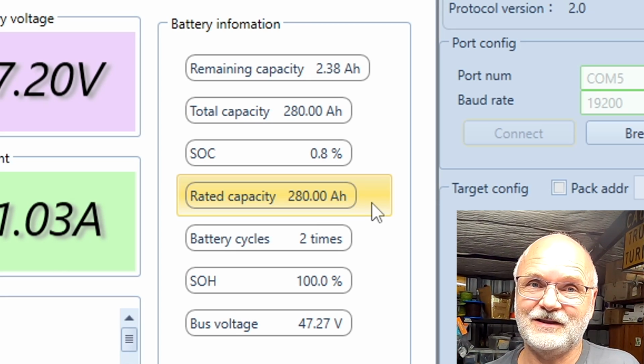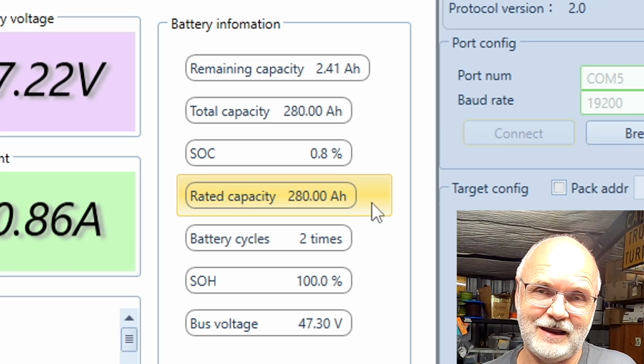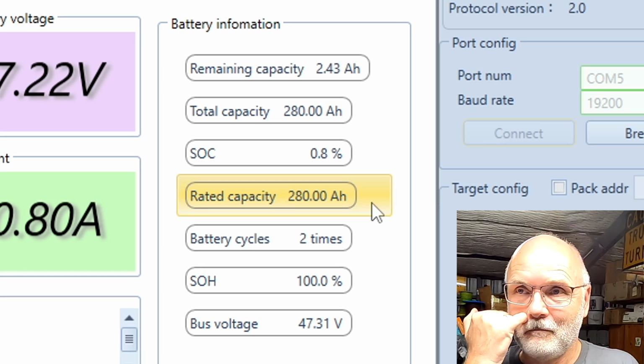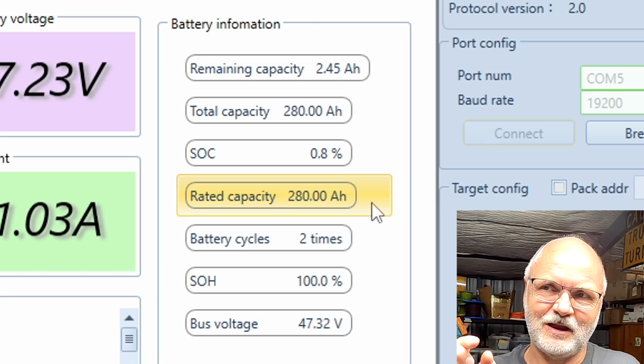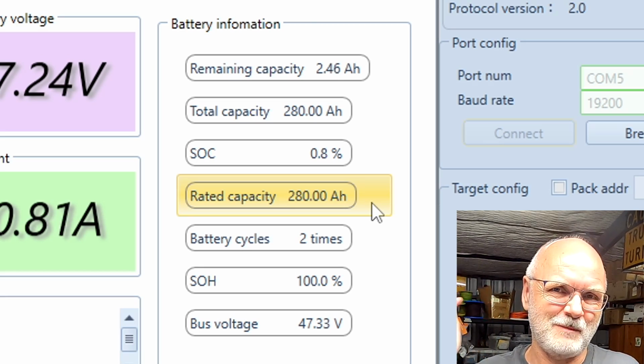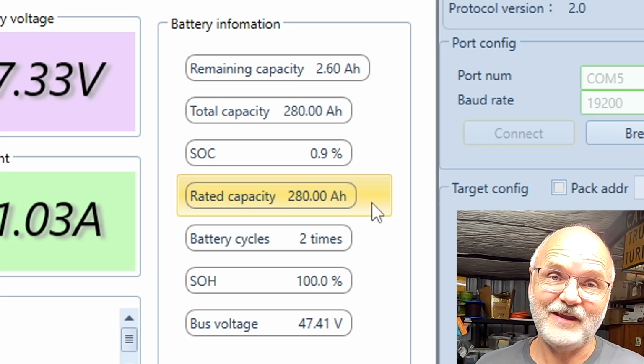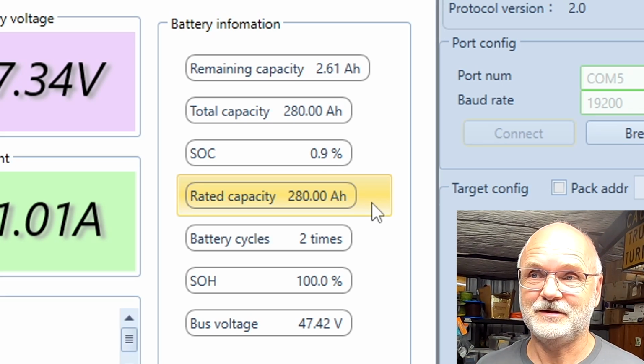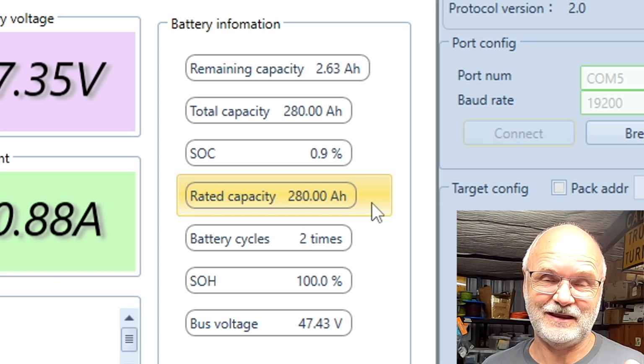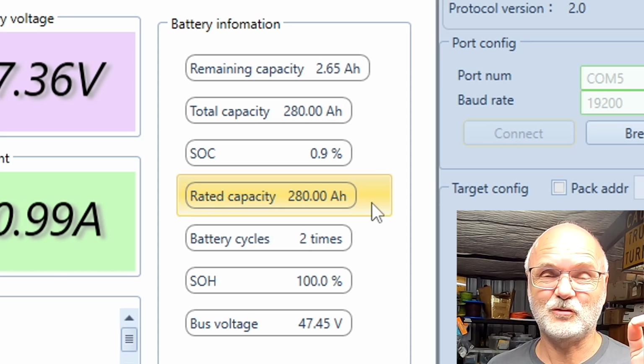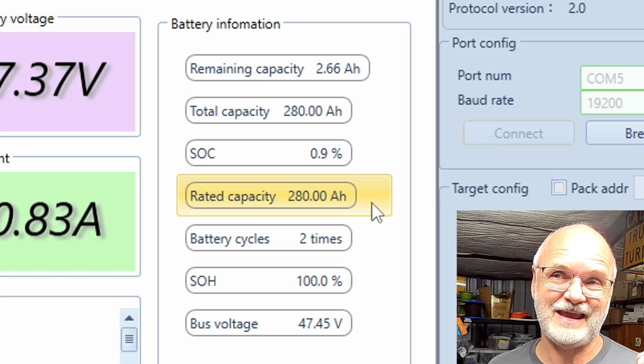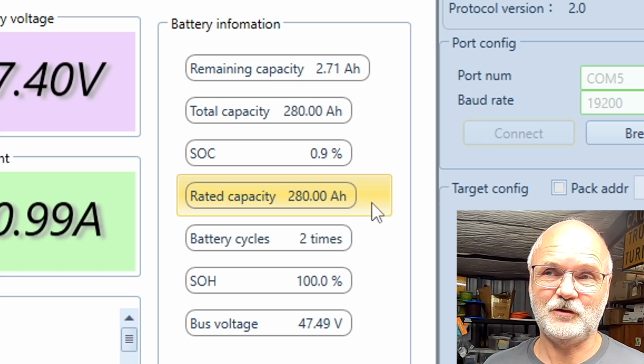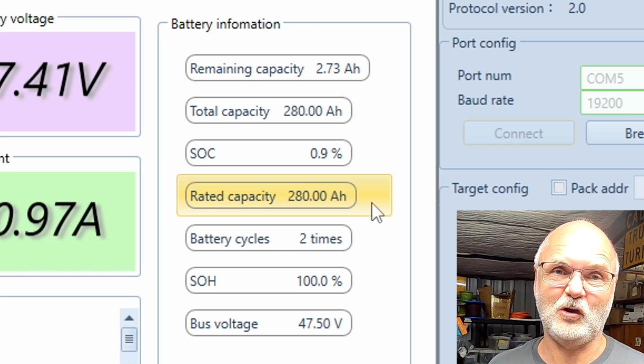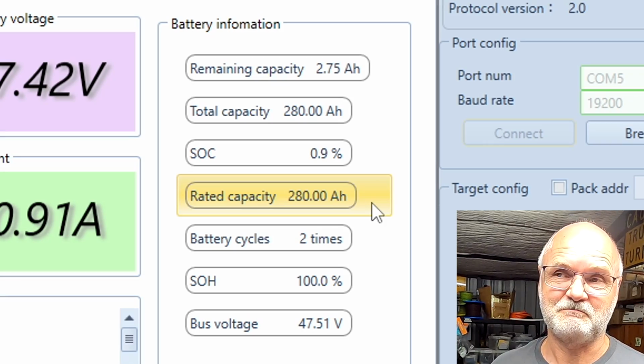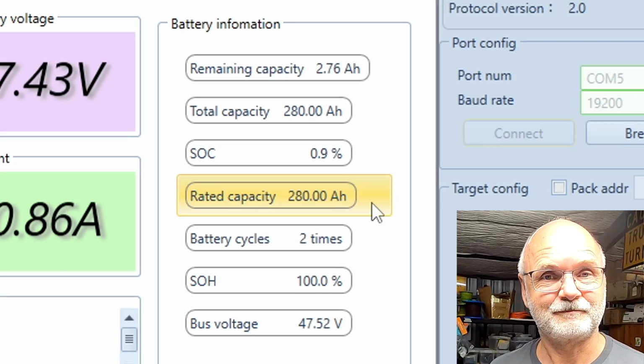I could do it manually and set the rated capacity from 280 ampere hours to 300 ampere hours, which is what we have measured. But I want to see if, once we fully charge the battery again, it updates automatically. The Pace BMS does this perfectly, it measures and updates the settings automatically, so you know exactly the real capacity of your battery every time. The Seplos or JK BMS just follow what you have set manually. But let's see when we fully charge.